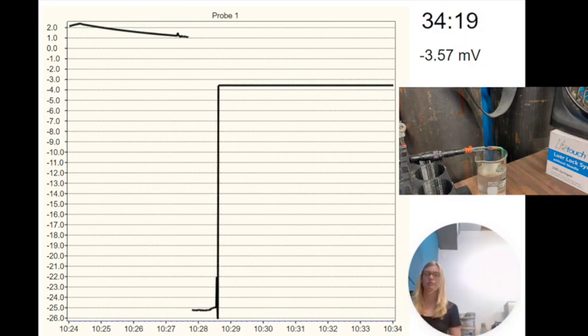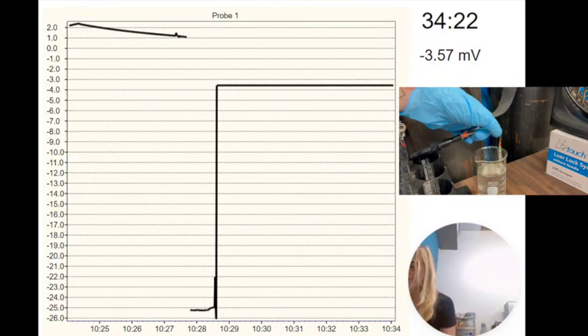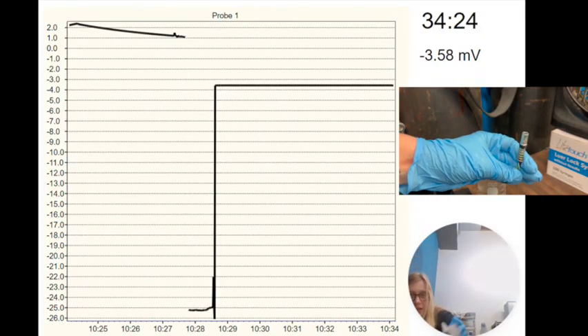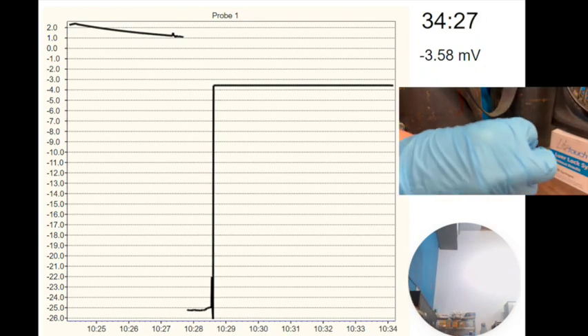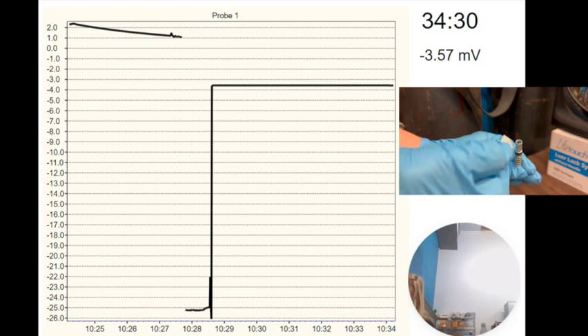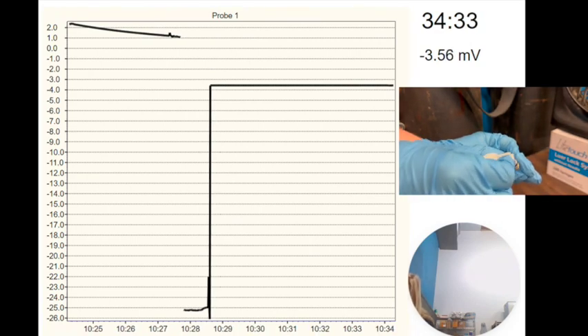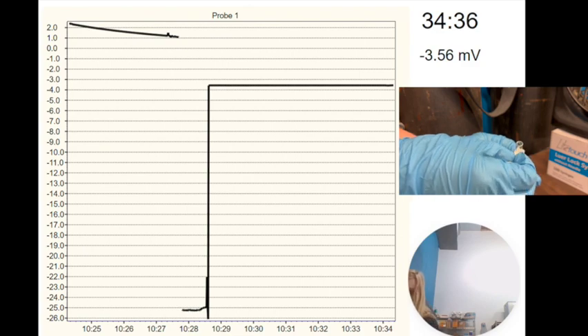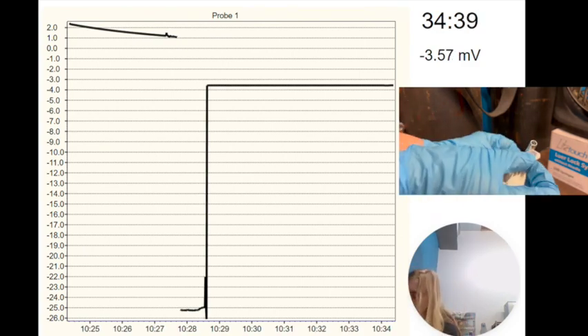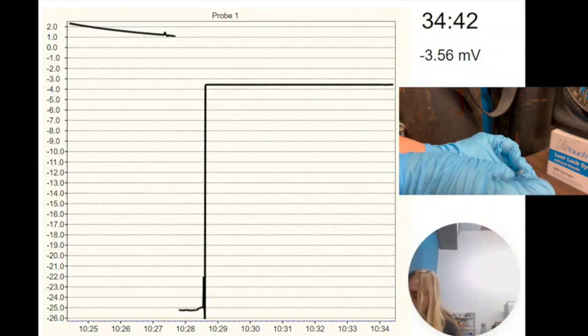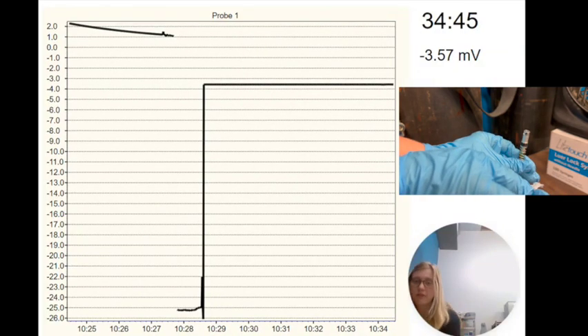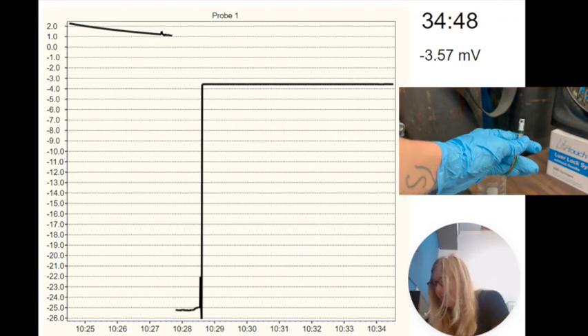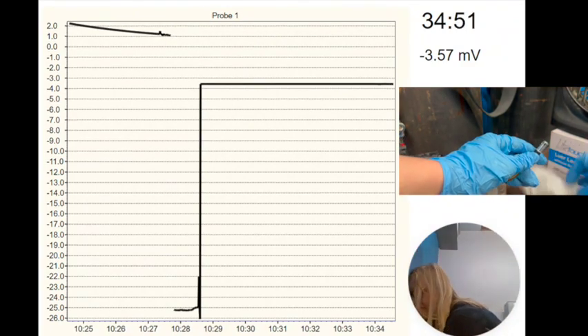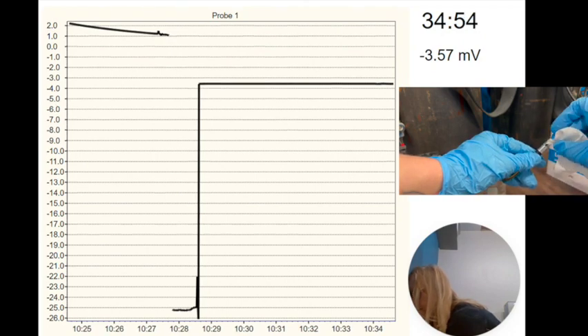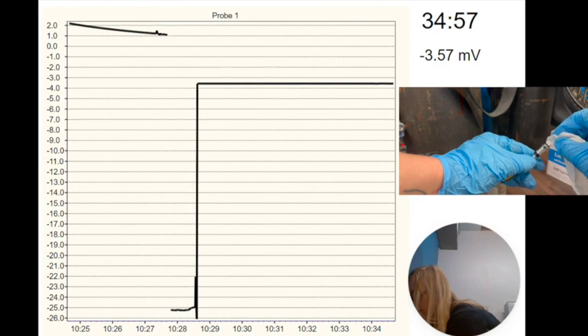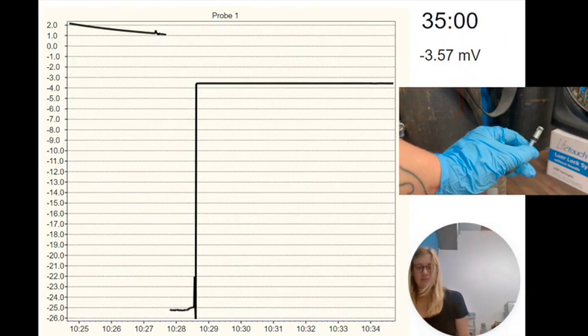And if I take it out of water, like I have done with all the other probes, at 34:20, fan is going, taking my napkin and dabbing the sensor face dry. We see that it is not drying out. So even when I triple check with my napkin, force it in front of the fan, it is not moving. The voltage is staying the same.